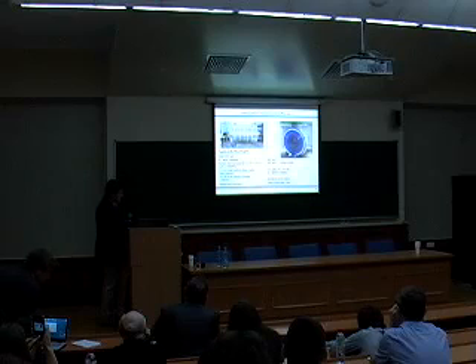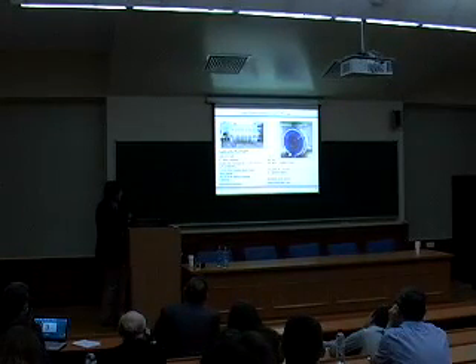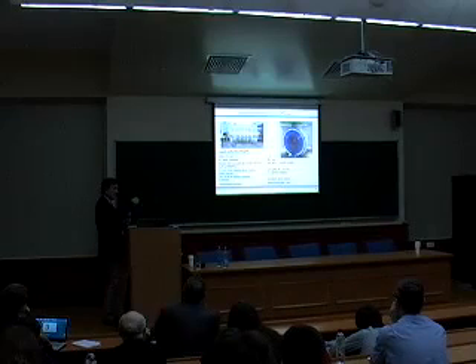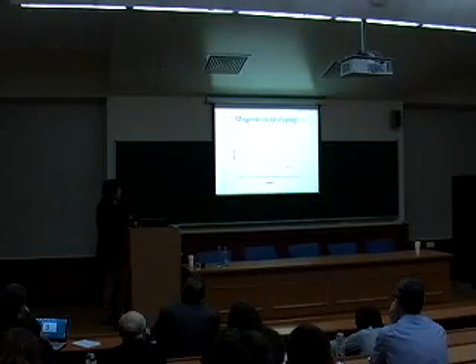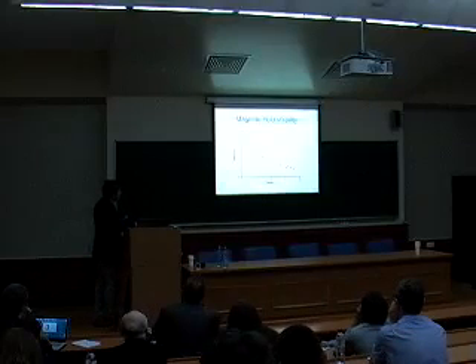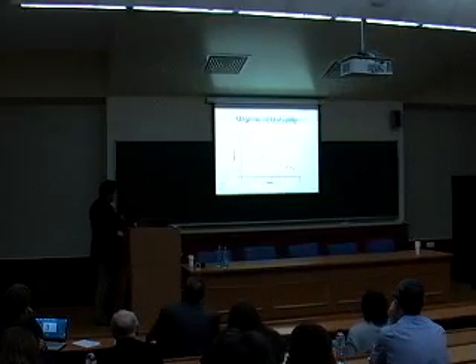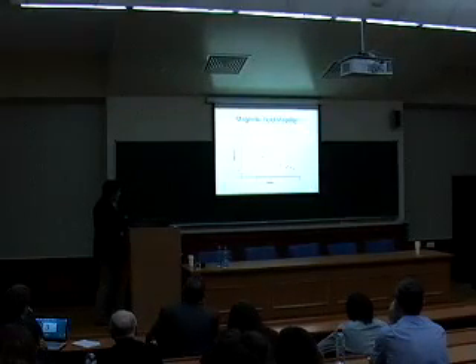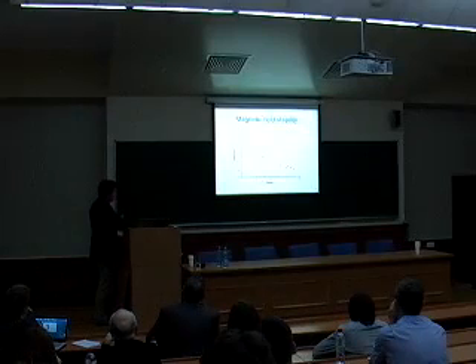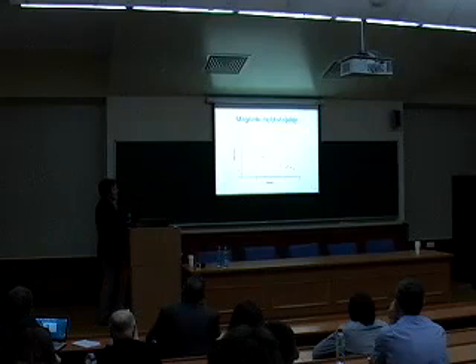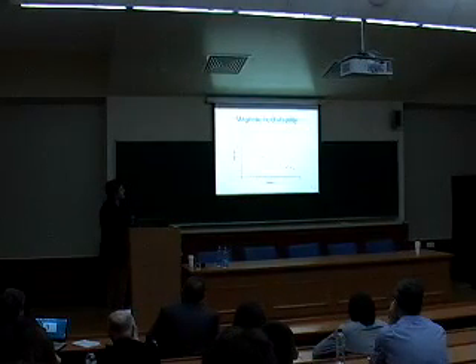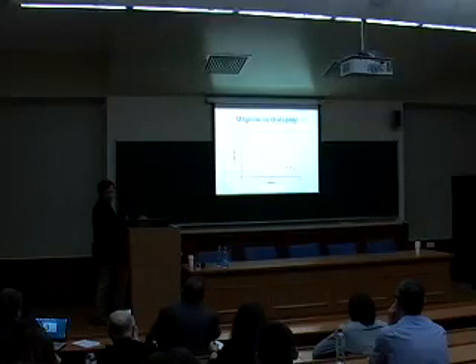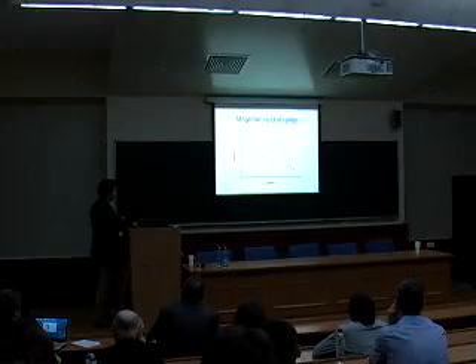Okay. And on the top of this magnet, you have here the cryo-refrigerator, which refrigerates vapor to liquid, and the liquid comes to the helium vessel. So this is a very important curve, magnetic field stability. You see that after 300 hours, we have saturation practically, and the field stability is 0.01 ppm per hour. This is the same number given by Siemens and other manufacturers.